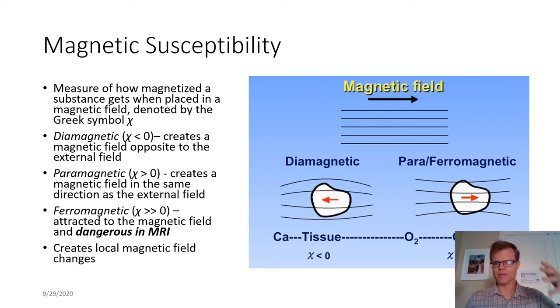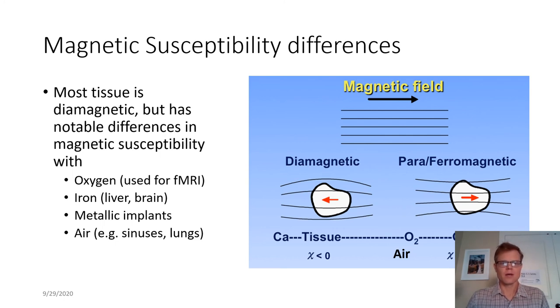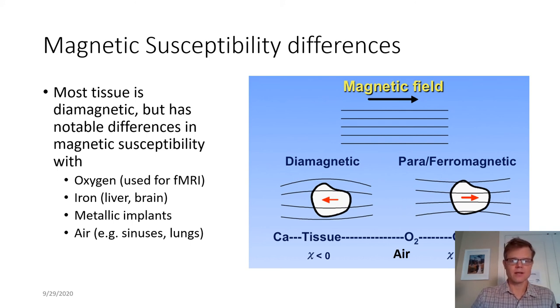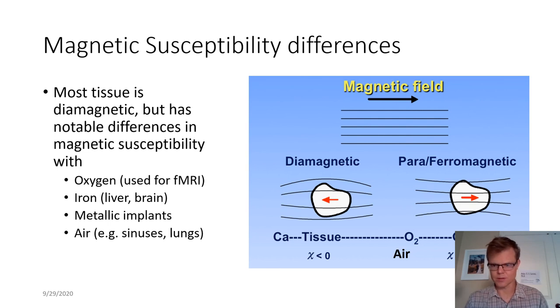With a big magnetic field and our substance in there, it creates little changes — that's what these bumps in the line illustrate, the little local changes in the magnetic field. The differences in magnetic susceptibility are actually used for contrast. We're mostly diamagnetic; oxygen is slightly paramagnetic; iron is very paramagnetic. Metallic implants will be paramagnetic — not ferromagnetic, otherwise we couldn't bring people in with them — but most medical implants are now MRI compatible. Air in the body is slightly paramagnetic and will also change the signal a little bit.